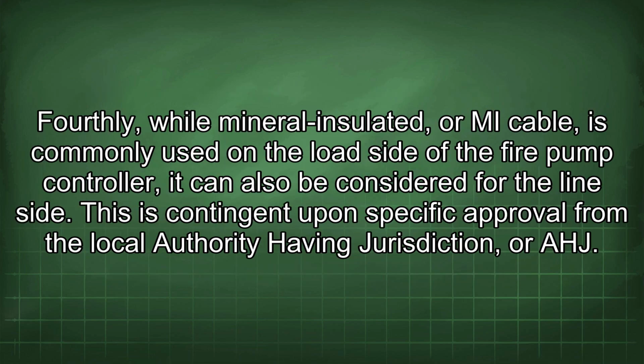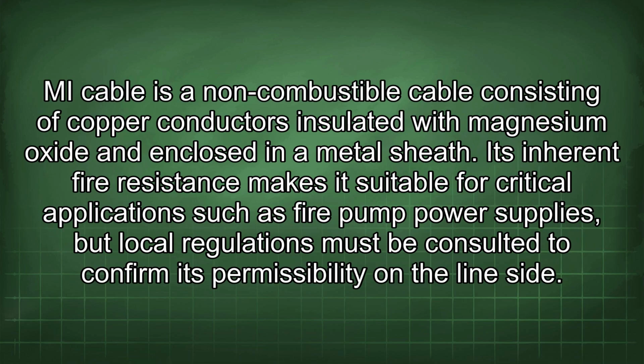Fourthly, while mineral insulated MI cable is commonly used on the load side of the fire pump controller, it can also be considered for the line side. This is contingent upon specific approval from the local authority having jurisdiction, or AHJ. MI cable is a non-combustible cable consisting of copper conductors insulated with magnesium oxide and enclosed in a metal sheath. Its inherent fire resistance makes it suitable for critical applications such as fire pump power supplies, but local regulations must be consulted to confirm its permissibility on the line side.